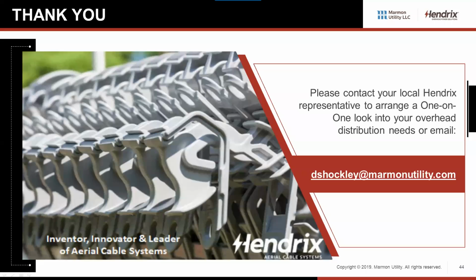We had a question about the 115 system. What is the top ampacity rating for that? I will tell you that I talked to Brian during the chat, and it looks like it's a 1033 mil cable. That is the largest cable that can fit in the 115 system. And at 90 degrees, that will allow you 983 amps. So it looks like it's around 980 amps as the top ampacity on the 115. So I answered that one for you, Ted.